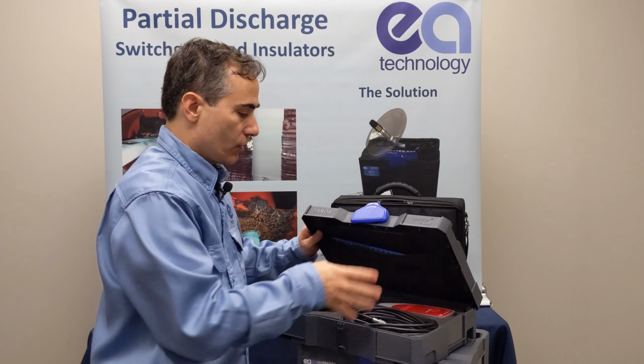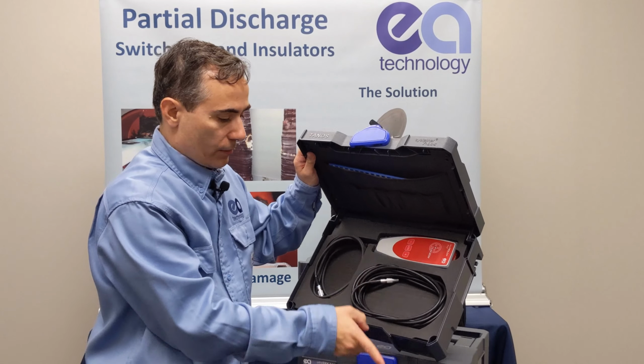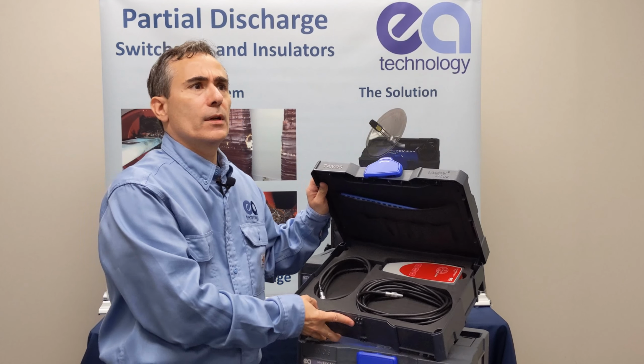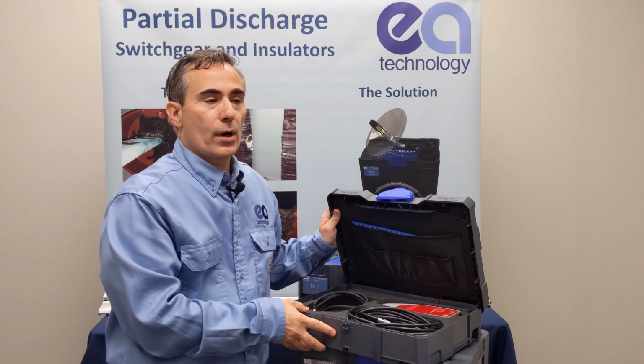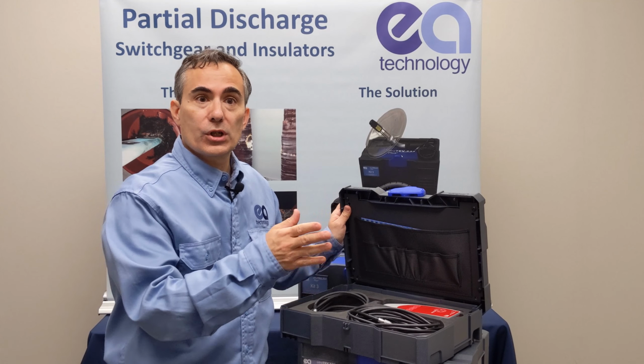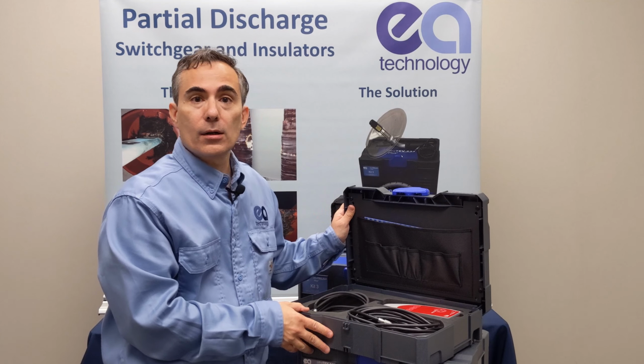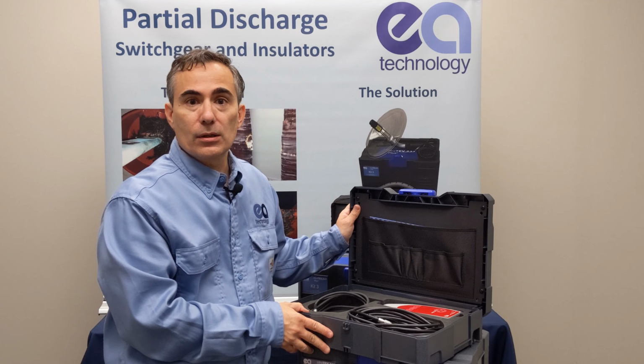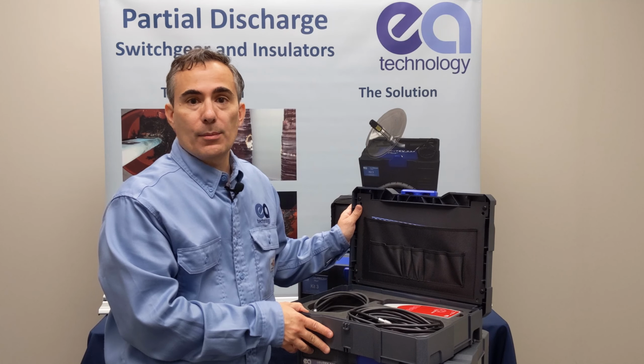It's a TEV sensor in the same form factor as the UltraTEV. If you have switchgear cabinets where you have TEV but you're not sure which cabinet it is, you could use the locator. It uses time-of-flight technology to determine which cabinet it would be.